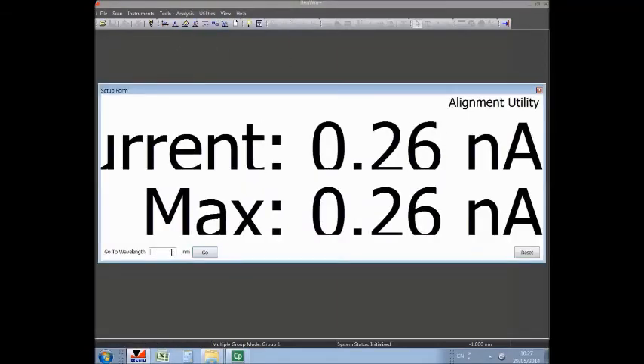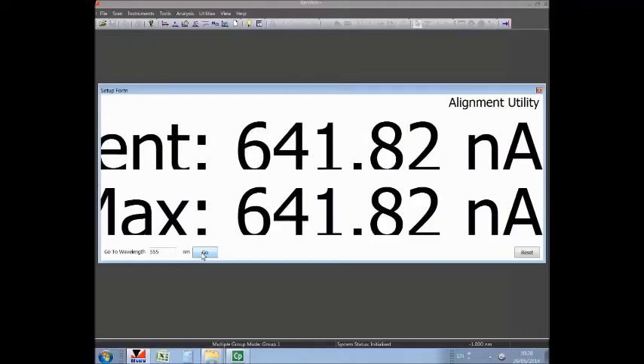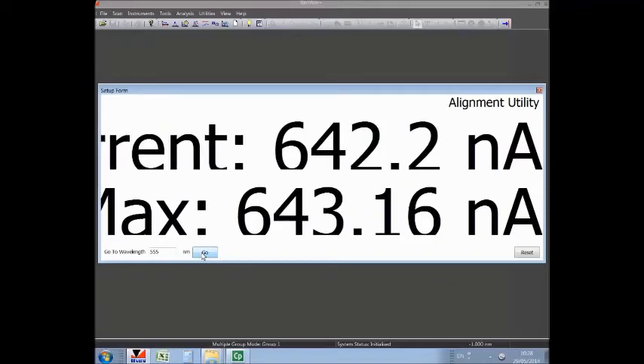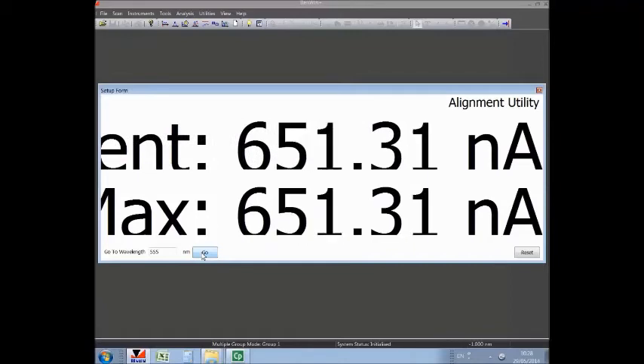Having set the source 200 millimeters from the front face of the D7 diffuser, we can align the source using the alignment utility. And for this white light source, 555 nanometers will be a suitable wavelength at which we can do this. Hit go to set the monochromator to 555, and we will read the signal, and we can then adjust the position after the amplifier has ranged to obtain a maximum.